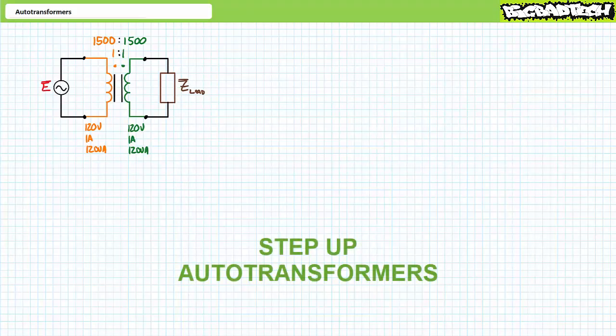Let's now take a look at step-up autotransformers. As previously, it's perhaps easiest to visualize a step-up autotransformer by first imagining a traditional one-to-one transformer with primary and secondary windings having identical turns ratio. Let's say 1,500 turns in the primary and 1,500 turns in the secondary. As previously, let's say this traditional transformer has a 120 volt rated voltage, a 1 amp rated current, and a power rating of 120 volt amperes. Let's again say this transformer weighs 8 pounds.